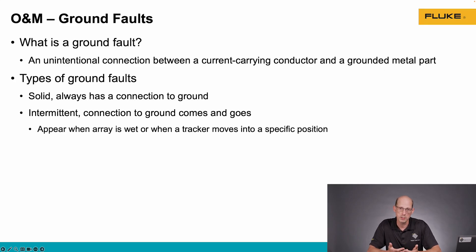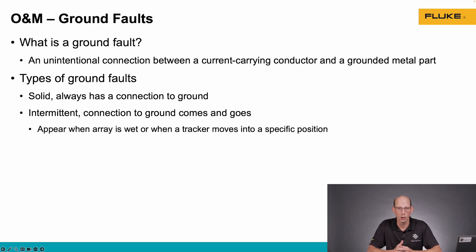There are two types of ground faults generally. A solid ground fault is a fault where the connection is solid — it's always present. The second type is an intermittent ground fault where the ground fault comes and goes. There are many causes of intermittent ground faults; it could be under wet conditions the ground fault appears, or maybe the wire is being pinched by a tracking array when it gets into a certain position.